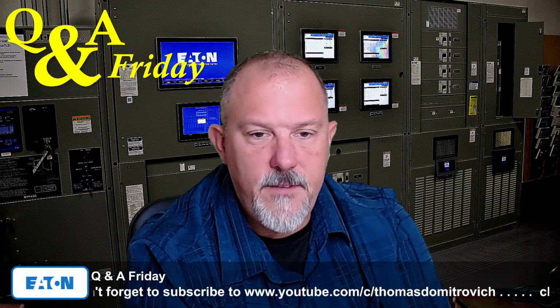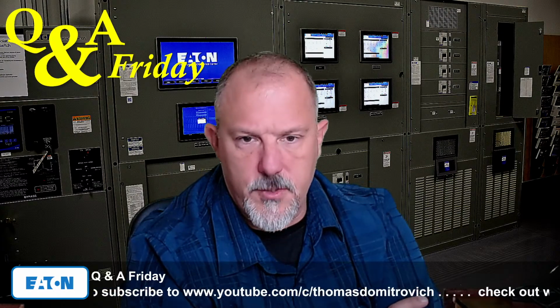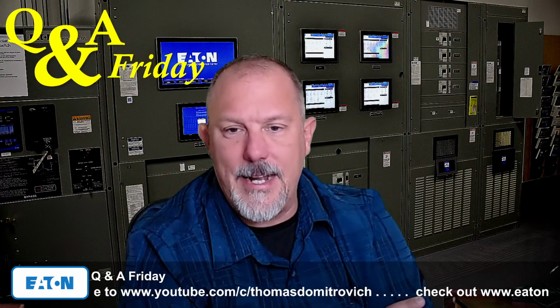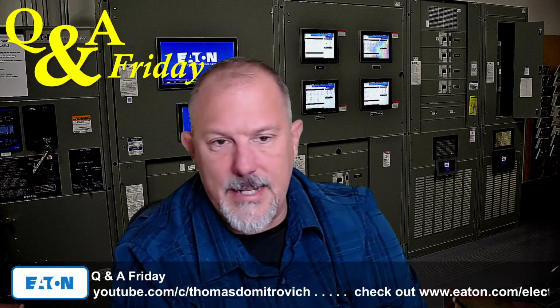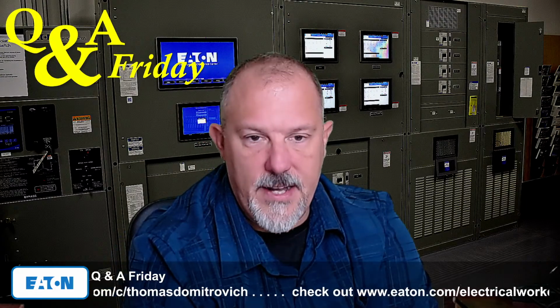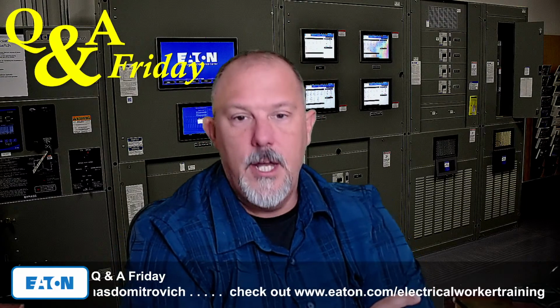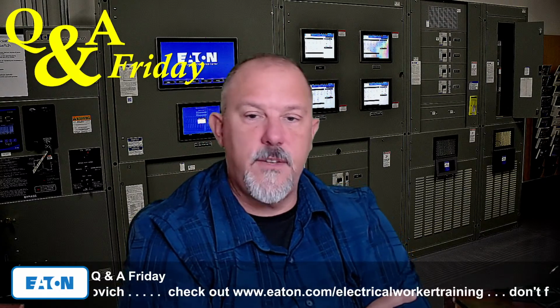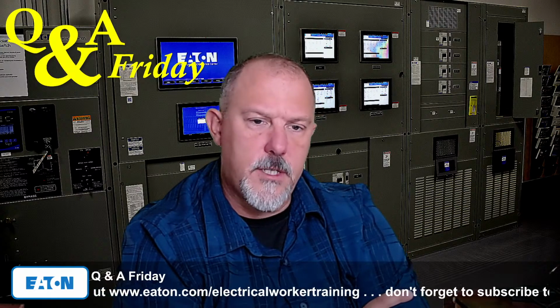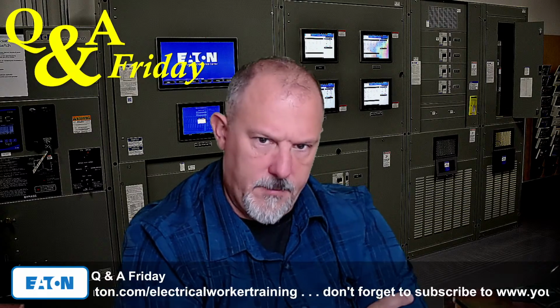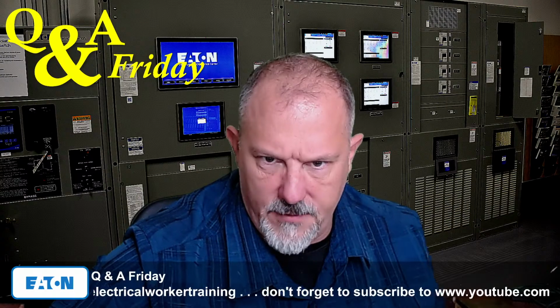He says he's seen Eaton fused bolted pressure switches that actually say you have to use 90 degree C rated conductor, but size the ampacity at 75 degree C ampacity max. You could not use a 60 or 75 degree C conductor in this equipment. This goes to the concept of the conductors absorbing some of the heat. Temperature may be more than 75 degrees C.